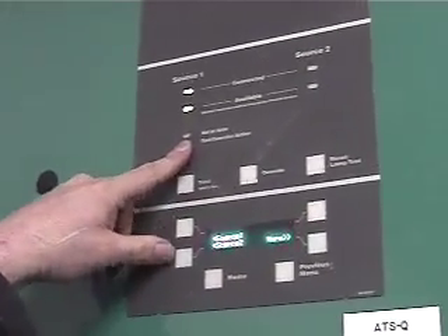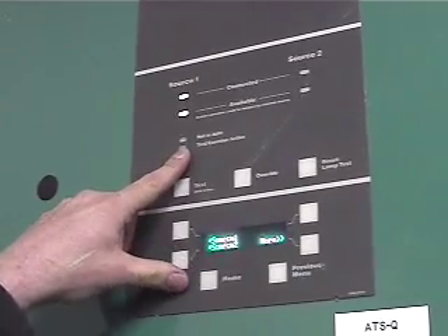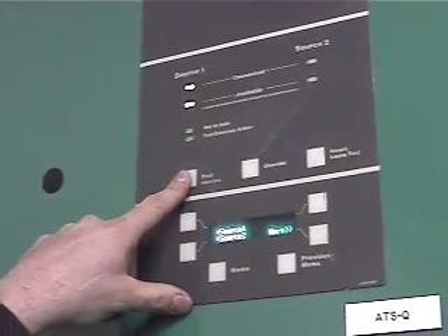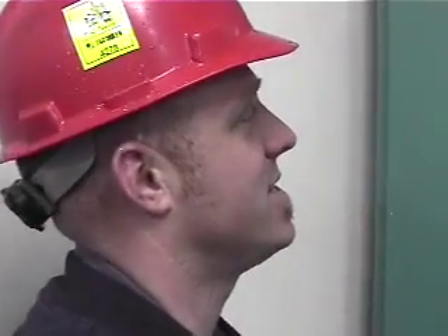Not auto is if it's not going to work automatically. Test is if I push and hold this test button, it's going to put it into test mode. Now, one thing to be aware of is that a test is different than an exercise. A lot of people get confused between the two. A test is I'm standing here pushing the button to make it do its thing. An exercise is it does it by itself. This has a clock inside of it that will start it and run it anytime we want it to. If you want to run Mondays at 7 o'clock in the morning, it'll do it by itself.